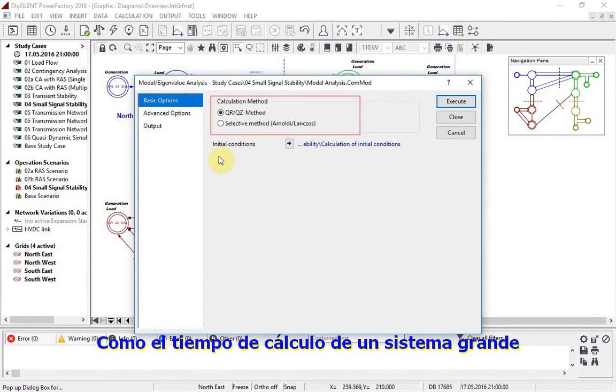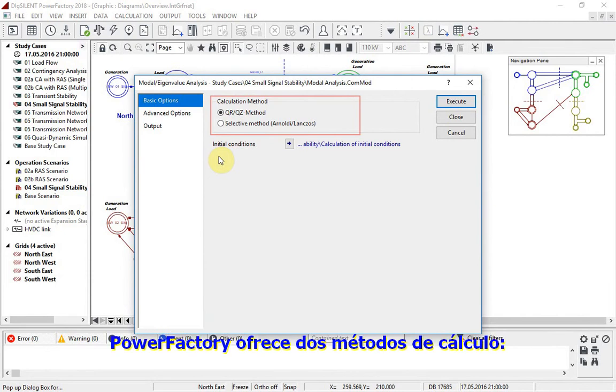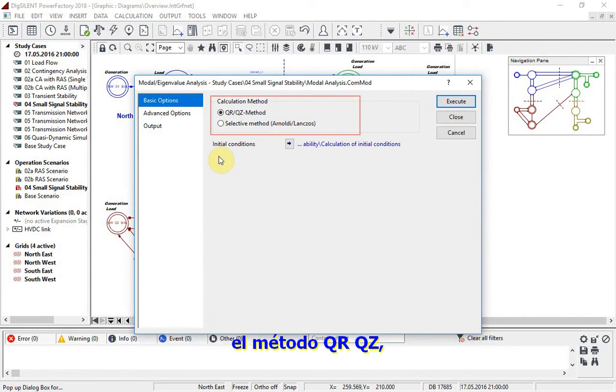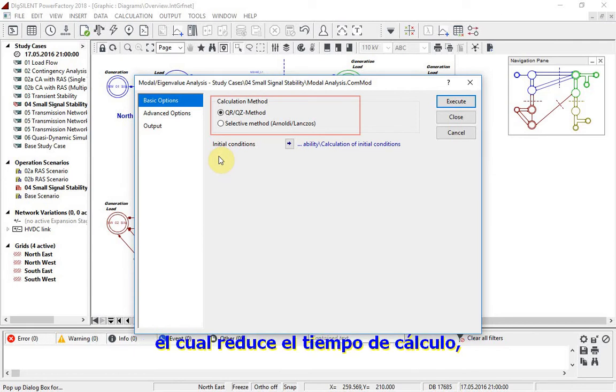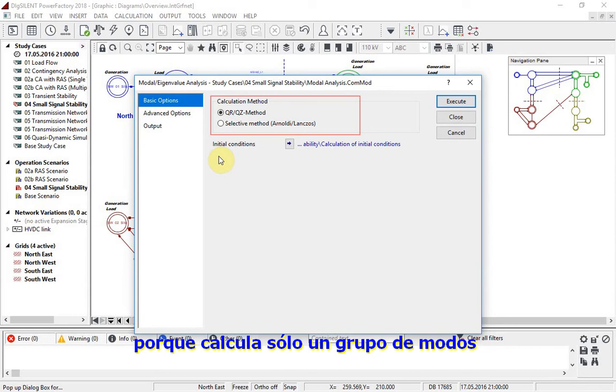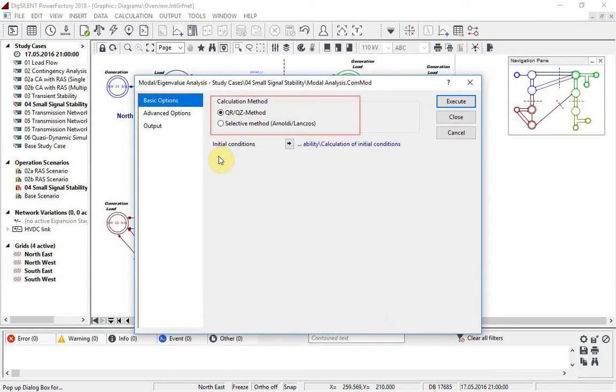As the computation time for a large system can be too time consuming to be practical, Power Factory offers two computation methods: the QRQZ method, which considers all modes, and the selective modal analysis method, which reduces computation time because it calculates just a number of modes within a previously identified frequency range.